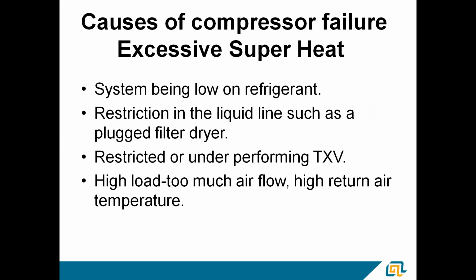Causes of compressor failure. Number one cause I've seen is excessive superheat. System being low on refrigerant, restriction in the liquid line, plugged filter dryer, what have you, restricted or underperforming TXV, or high load, too much airflow, high return air temperature. This one here, always measure your return air temperature. Don't guesstimate it off the temperature at the thermostat. That's something else that caught me a couple of times. You want to actually measure the return air entering the unit at the filter grill or the filter. Make sure that's what you're calculating stuff on. You could have a return duct broken apart in the attic or something like that, and you're sucking hot air into it. So measure return air at the return to the unit.